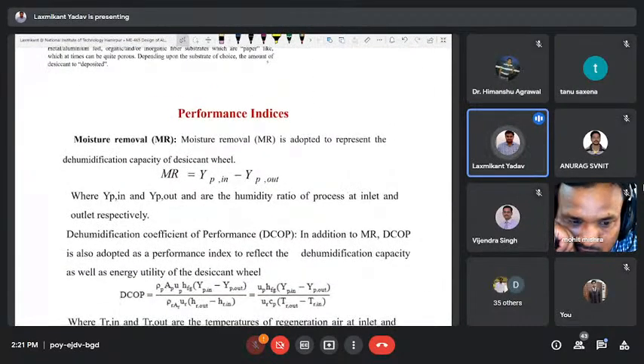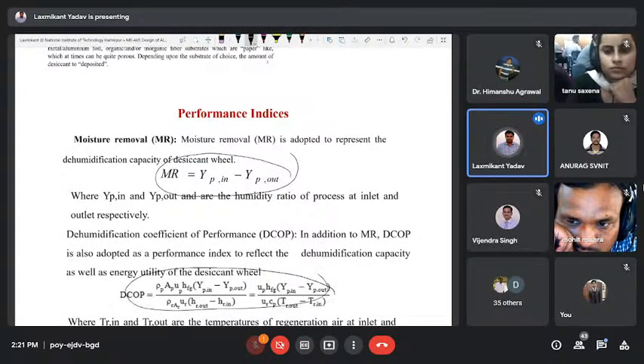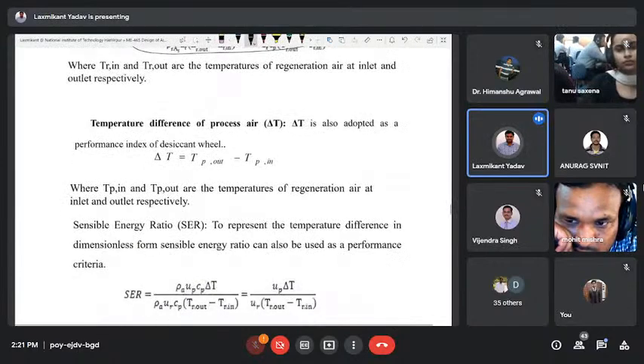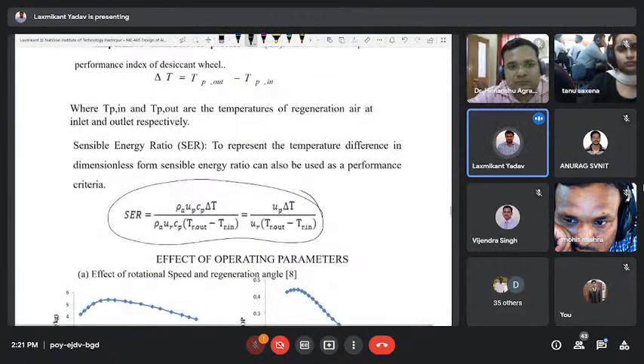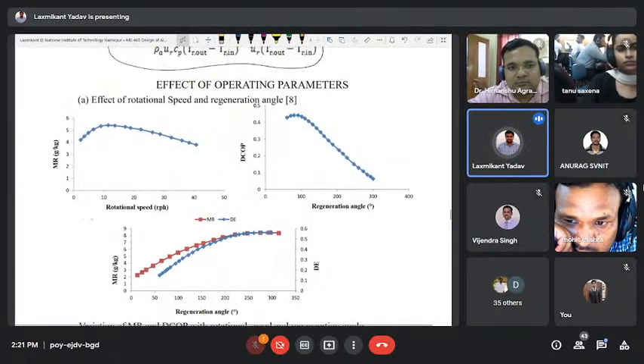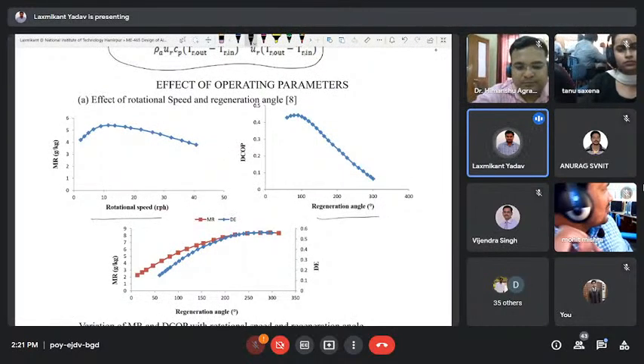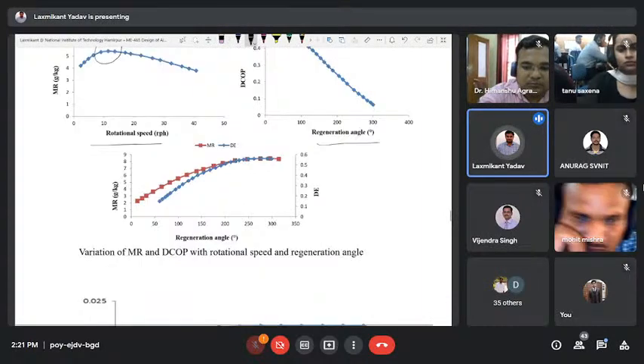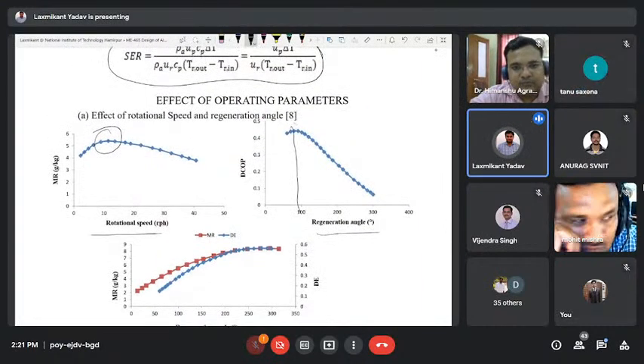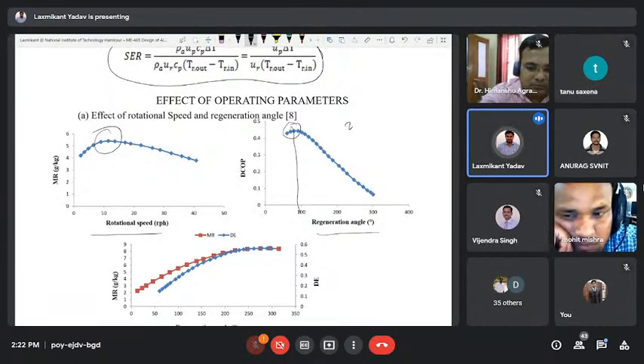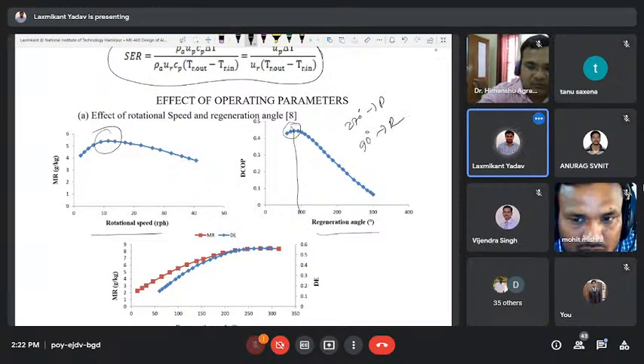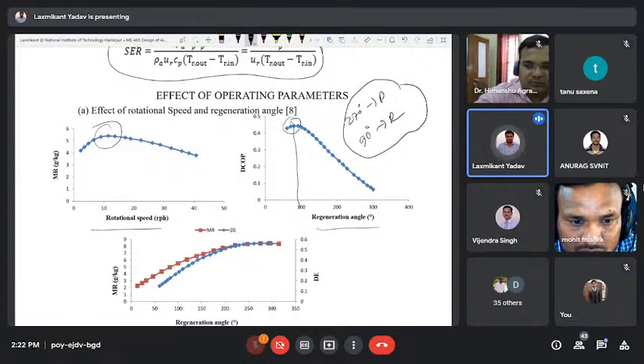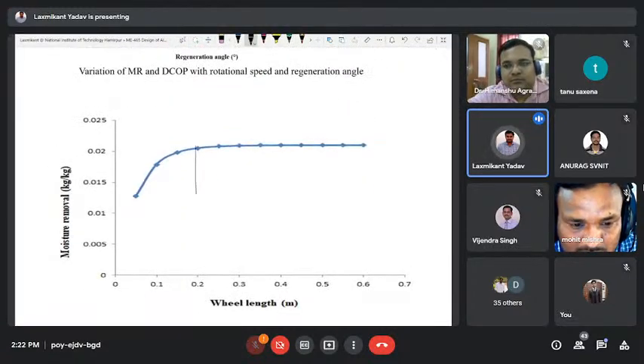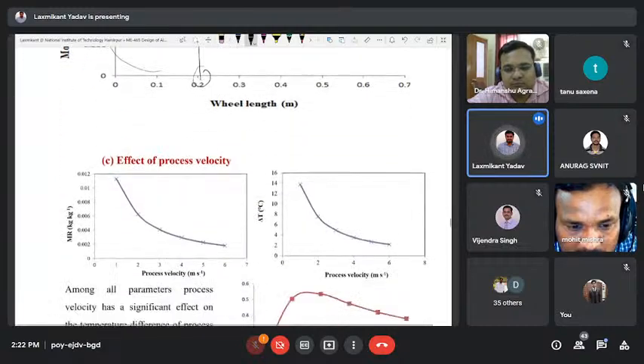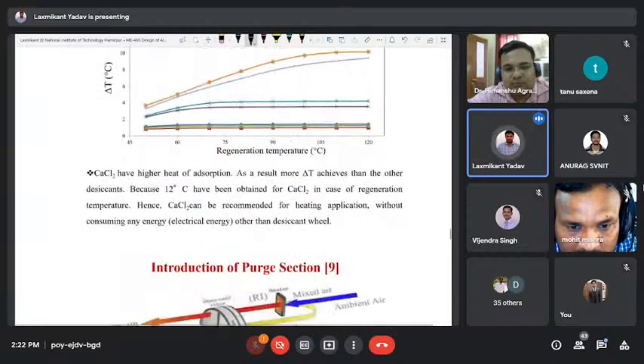Some performance indices are the moisture removal performance and the DCOP, the dehumidification coefficient of performance, which we calculate to indicate the performance of the desiccant wheel. Similarly, the sensible energy ratio. So these are the performance of the desiccant wheel at different rotational speeds and different regeneration temperatures. The optimum rotational speed is around 10 to 15 rph. Similarly, the regeneration angle is around 90 degrees. Generally the two-sector desiccant wheel that is available has 270 degrees of process section and 90 degrees of regeneration section, because the performance is higher. Similarly, the wheel length we generally found is around 0.2 meters. Generally, desiccant wheels of 0.1 meter and 0.2 meter length are available in the market. Okay, so these are some performance characteristics of the desiccant wheel.